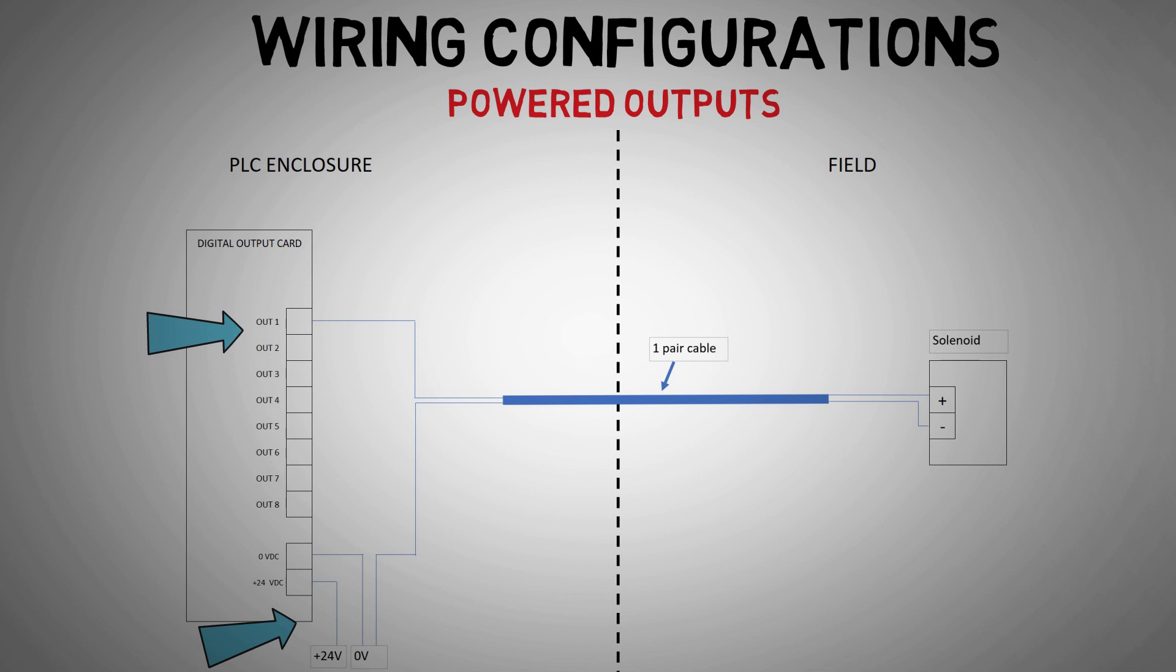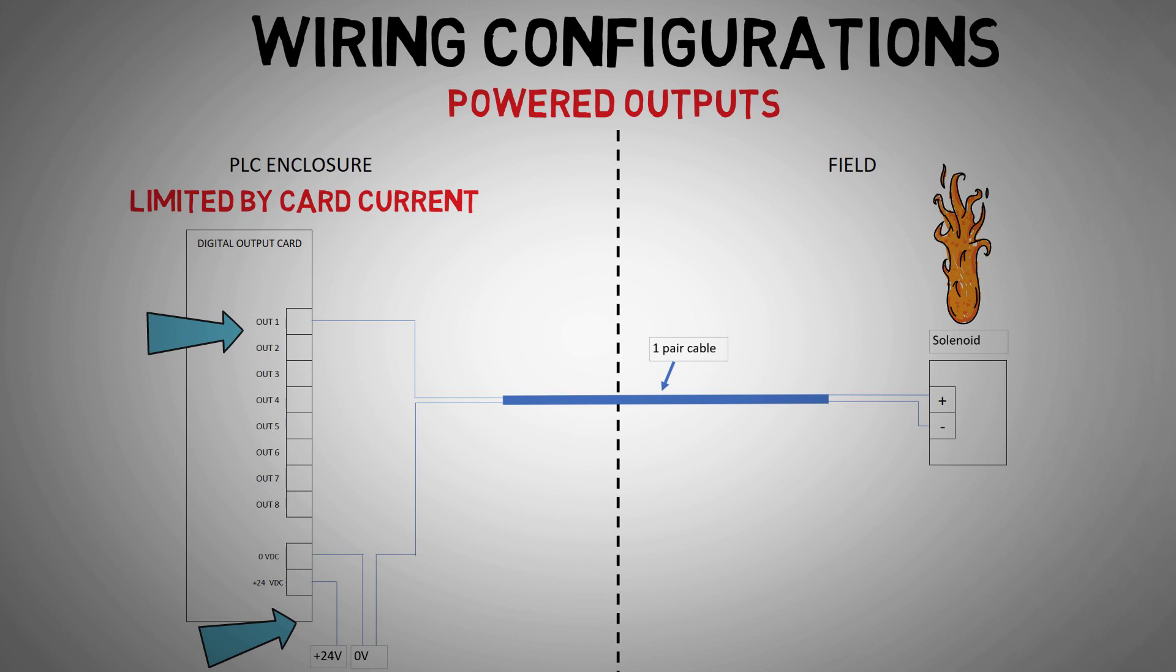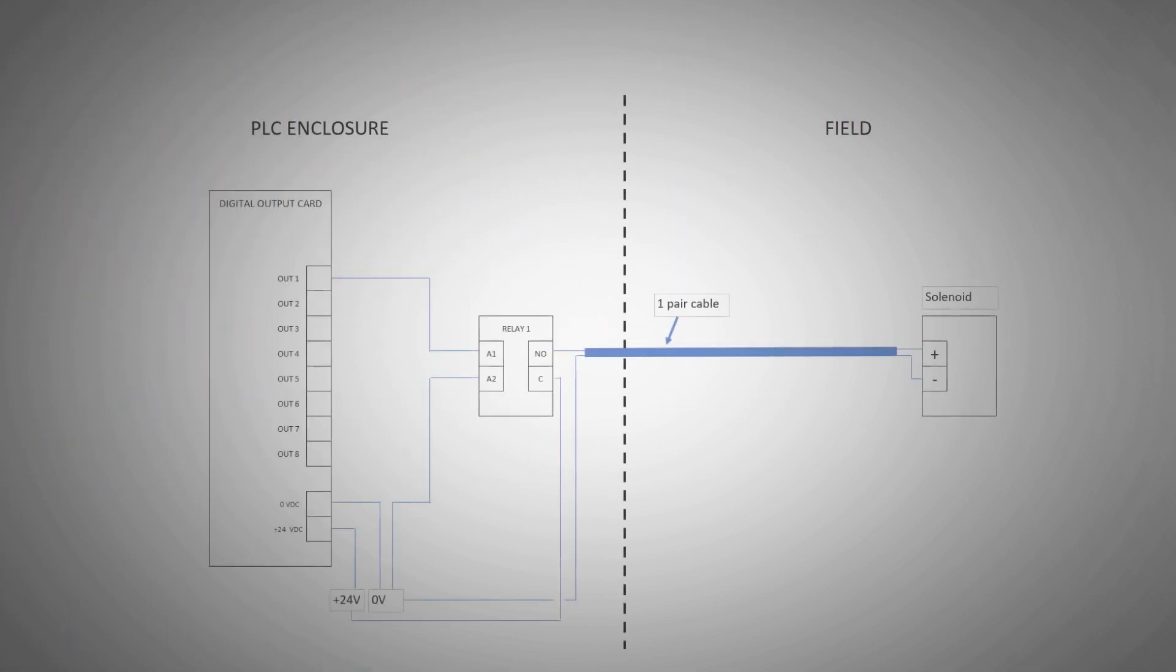This is a simple configuration, but a limiting factor is the current the output device requires. The required current may exceed what the digital output can provide, leading to blown fuses or damaged equipment. One solution is to use an interposing relay.